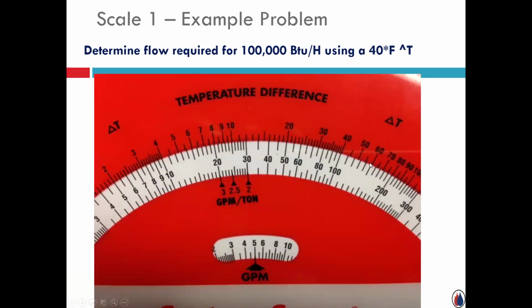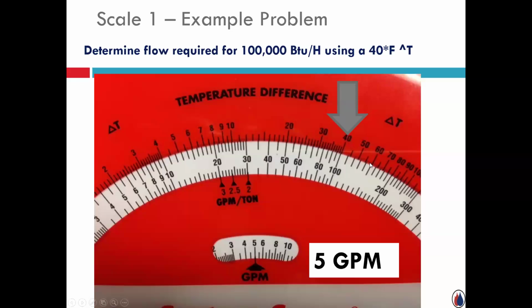What happens? What changes? So same thing. Scale one, line up the 100,000 BTUs, but now I'm going to line it up opposite the 40 degree delta T, and then read again in the smaller white window, the GPM, 5 gallons a minute. So whether it's 5 gallons a minute or 10 gallons a minute, they both can transfer, support, move, provide 100,000 BTUs. The difference being what's your delta T, what's your temperature drop that's going to take place between your heat exchanger, your boiler, or whatever it is that's providing the heat through your terminal units and then back to the mechanical room.